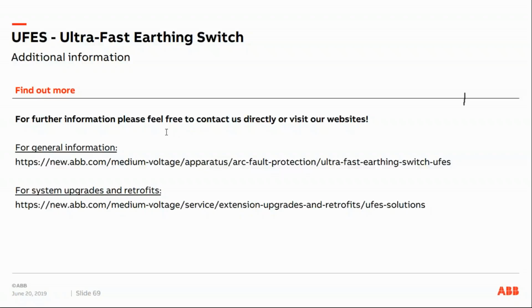One of the questions asked is, how is this different than a light sensing fault detector within the switchgear? Is it the fact that the UFES directly shorts to ground instead of triggering a traditional breaker to open? Basically, yes. What's happening here is that the UFES can detect, in combination of current and light sensing, and with the help of our control unit, the fault much faster than your conventional breakers. It will ground the short circuit in less than 4 milliseconds. So basically your main benefit is the time aspect here before any heavy damages can even apply to your system.